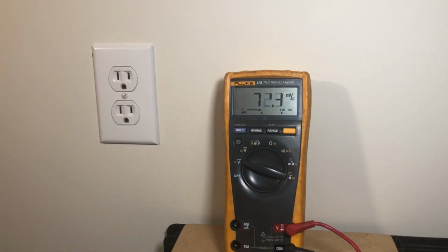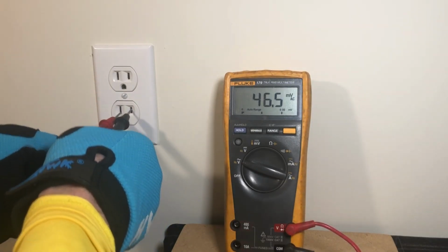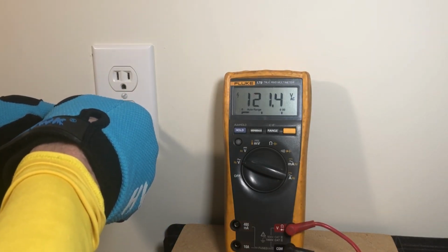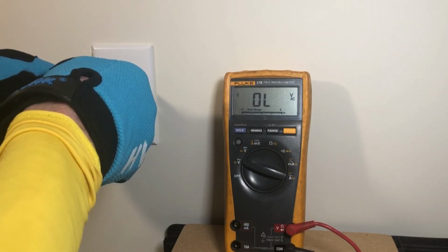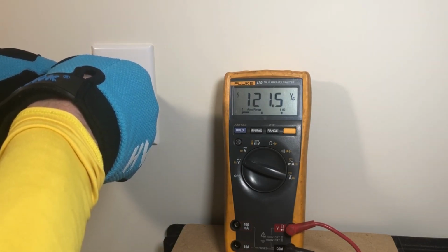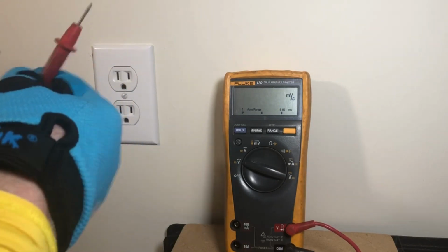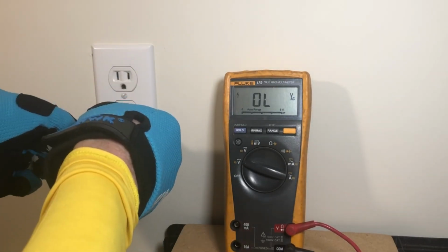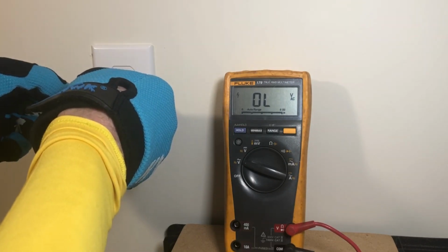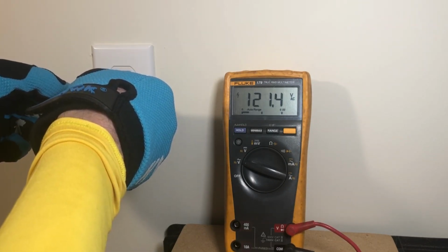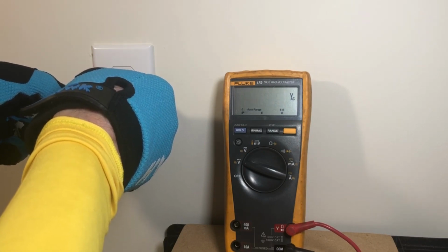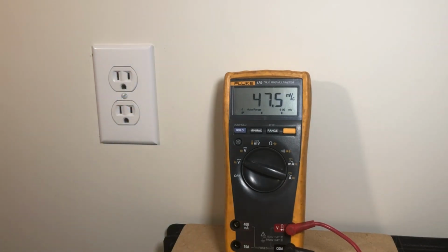Turn the multimeter to AC volts and insert the meter probes into the slotted openings. Since this is AC voltage, the polarity of the meter leads is not important, meaning red or black can be inserted into either slotted hole to achieve the same reading. You will clearly see whether this outlet is on or off. If 120 volts AC is displayed on the meter screen, this proves that the outlet is live. In other words, it is powered up and supplying electricity at its output slots.